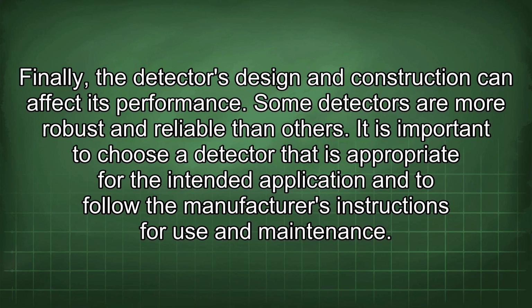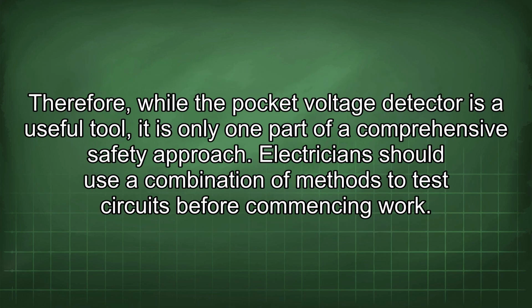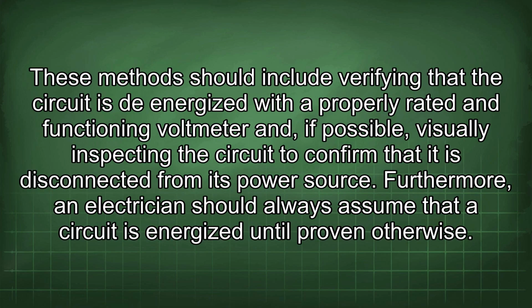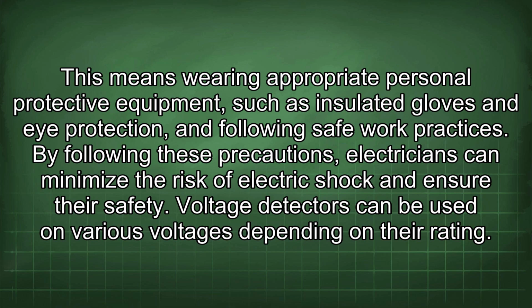Therefore, while the pocket voltage detector is a useful tool, it is only one part of a comprehensive safety approach. Electricians should use a combination of methods to test circuits before commencing work. These methods should include verifying that the circuit is de-energized with a properly rated and functioning voltmeter and, if possible, visually inspecting the circuit to confirm that it is disconnected from its power source. Furthermore, an electrician should always assume that a circuit is energized until proven otherwise. This means wearing appropriate personal protective equipment, such as insulated gloves and eye protection, and following safe work practices. By following these precautions, electricians can minimize the risk of electric shock and ensure their safety.